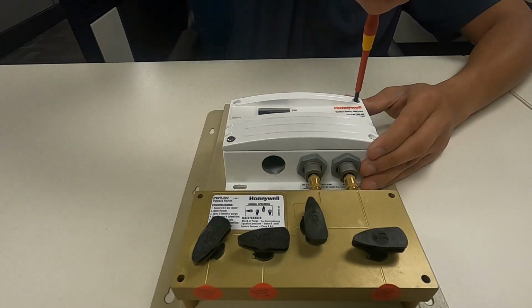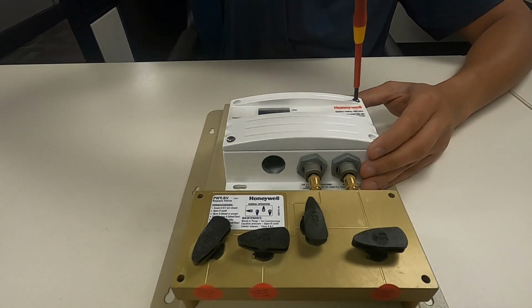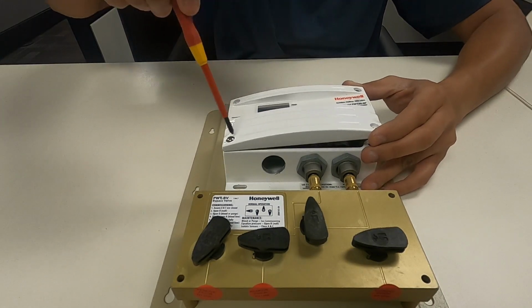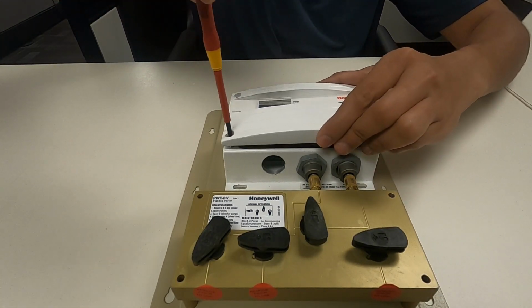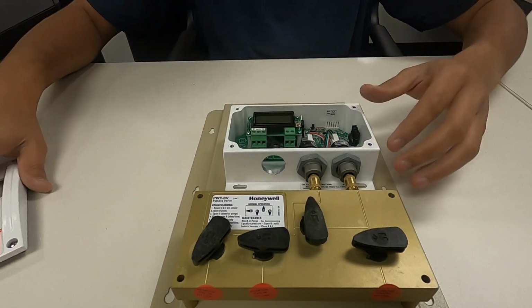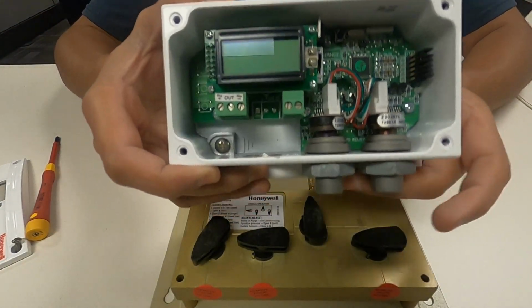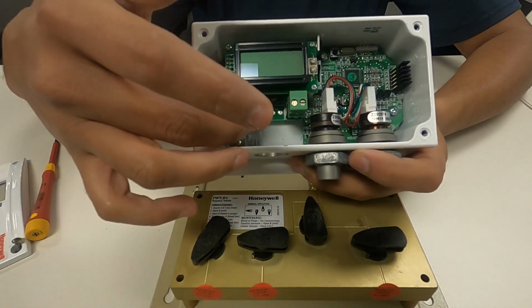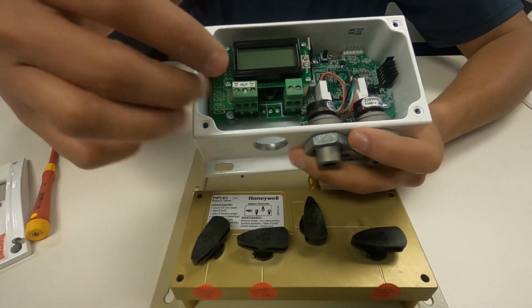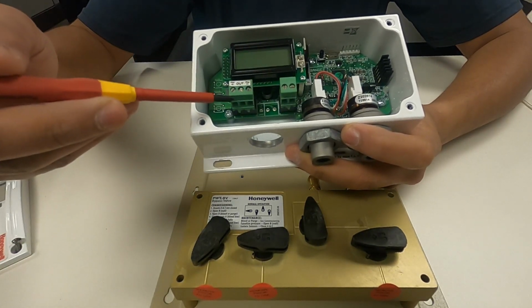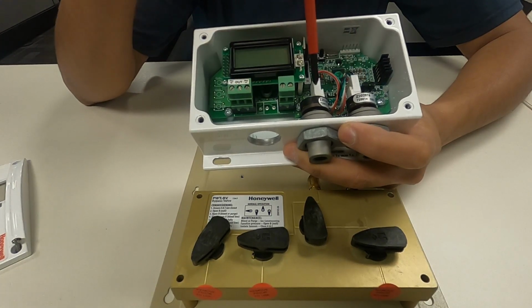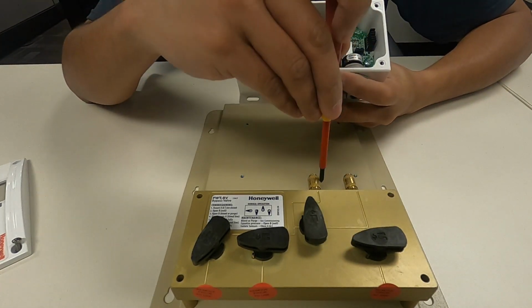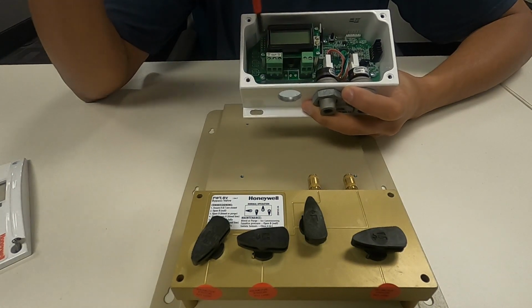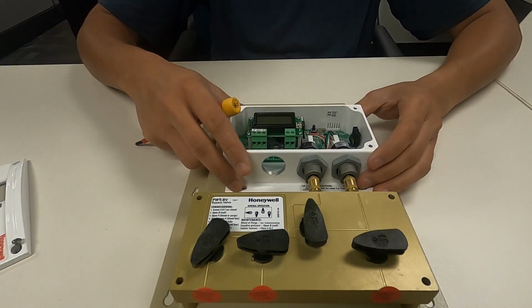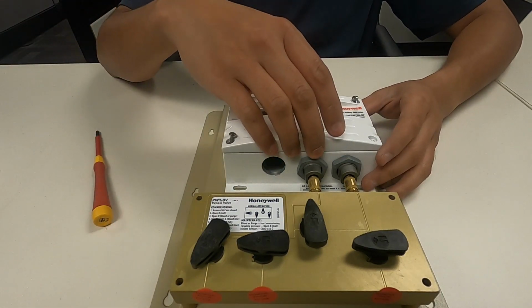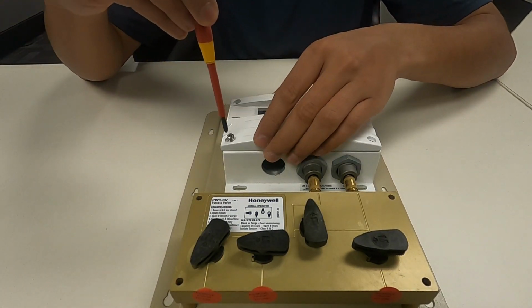So let's move on. When pressure sensors are used, the preferred signal type is the current signal, which is 4 to 20 milliamps. The reason we use a current signal is that the duct static pressure sensor is preferred to be at two-thirds of the duct coming from the unit. The long run of wire from the sensor to the controller will add resistance to the signal if we are using a voltage input, thereby hampering the pressure readings recorded at the controller.